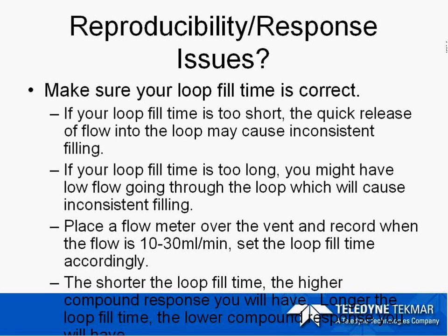Make sure your loop fill time is correct. If the loop fill time is too short, we will not fill the sample loop correctly, causing inconsistent loop fills and poor response. If it is too long, you may have low flow when the loop is back-flushing over to the GC. The shorter the loop fill time, the higher the compound response.